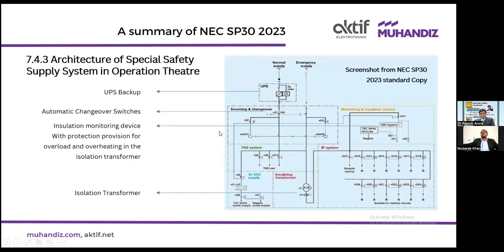Okay. This is a typical architecture, and this particular drawing is taken directly from the NEC standard. It shows a typical power supply system in a hospital, where there is a normal power supply and an emergency power supply, and there is a changeover switch which gives power to the UPS. There is an automatic changeover switch, and then we have an insulation monitoring device and an isolation transformer. These are all the components which are mentioned to be present in the typical power supply system in an operation theater.